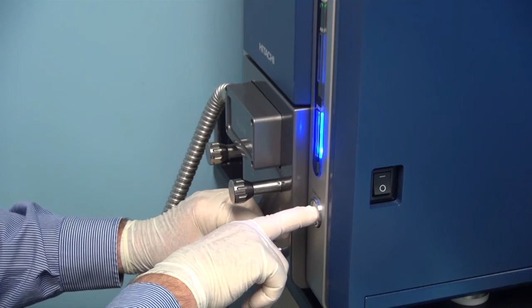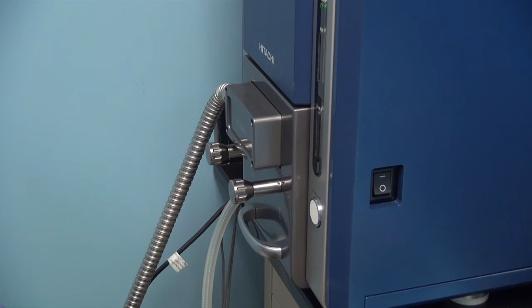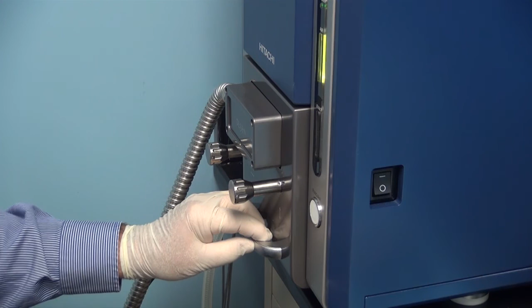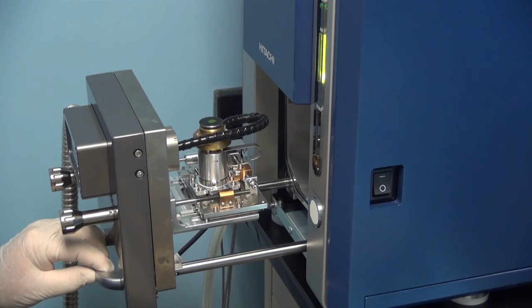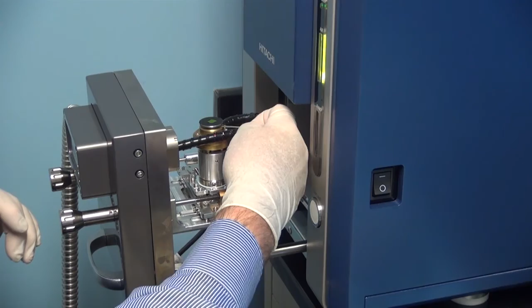Once your sample has reached room temperature, you're then ready to evac. Just push the same button. It'll take a minute or two for the vacuum to be released. Once the light stops flashing, you're ready to take your sample out. Use your Allen wrench to loosen it. The sample comes out, and you're ready to start with another sample.